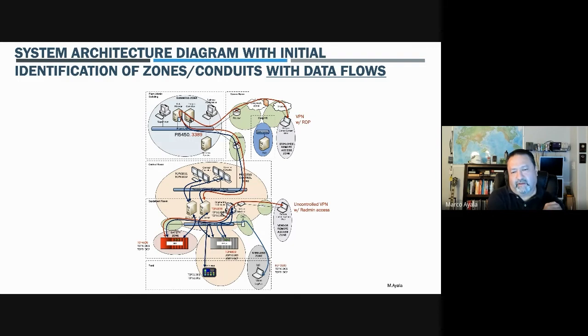Some of the other things too is that we do see asset owners that have a really good idea of what their data flows are, but when they go and actually do the capturing, they find out that there's things that are even at the lower sub-levels in the equipment room trying to reach out to the internet, trying to make communication with an application for update serving, to update the application. In other words, typical applications that you would say 'why do you have that application?' Well, that's how we read our vendor manuals. Let's take Adobe Acrobat for example. We still see Adobe Acrobat that are loaded on engineering workstations and even operator stations so they can read the actual manuals. You may have a heartbeat trying to come home to the application server or the app update. If you don't have a perimeter firewall or perimeter protection involved, that service could go out and maybe touch the internet. There's a lot of things that you can capture when you're doing your data flow analysis and capturing that and putting it into some kind of security event management. So it's very important.